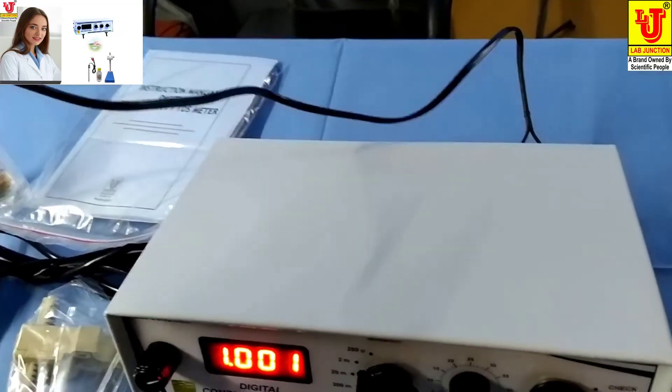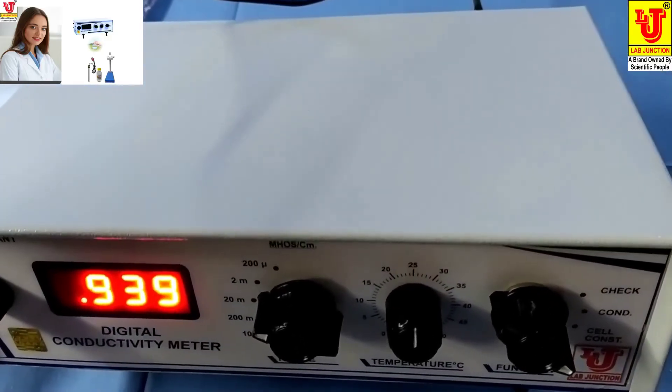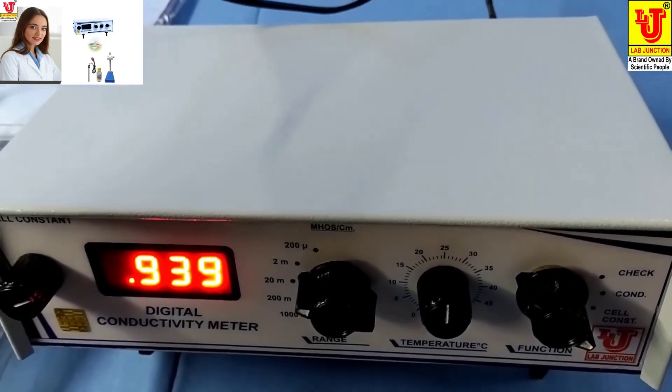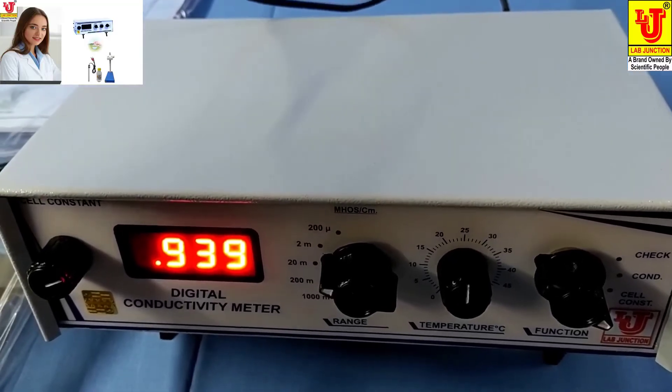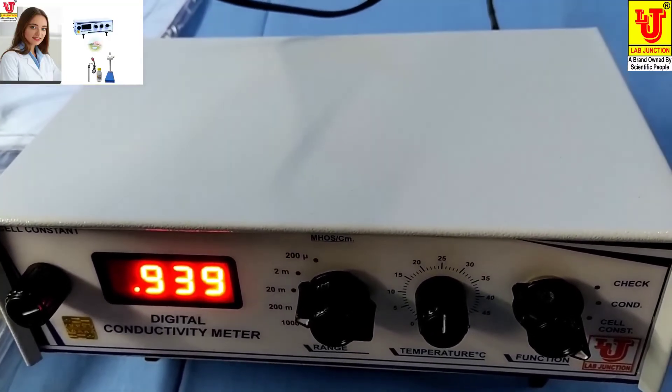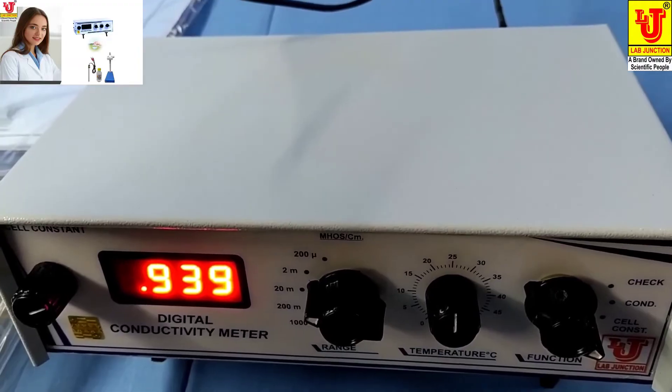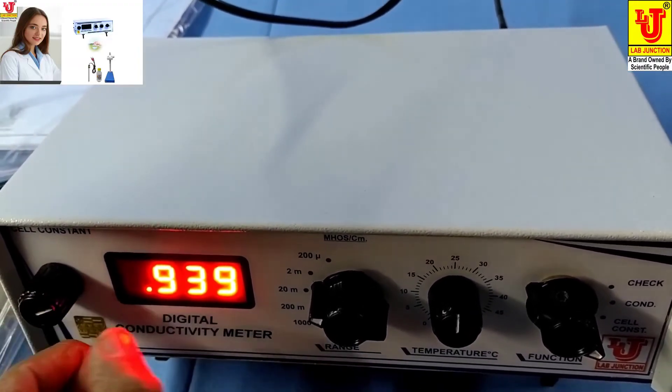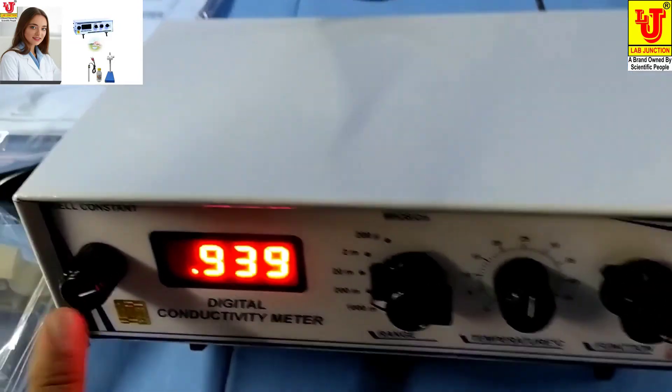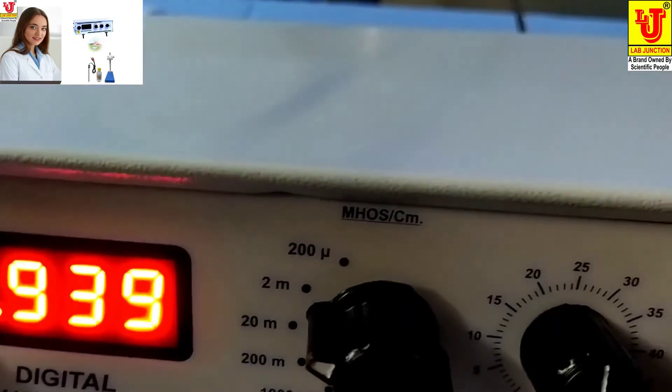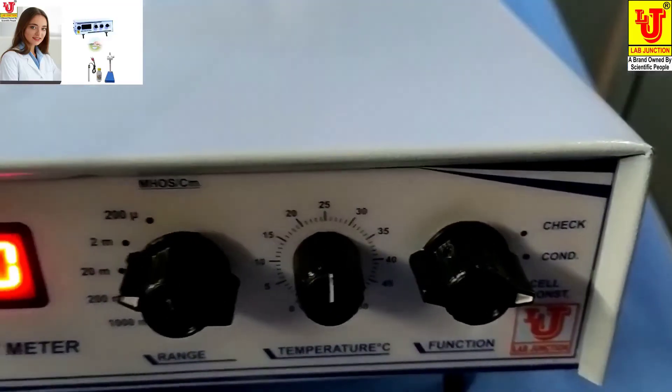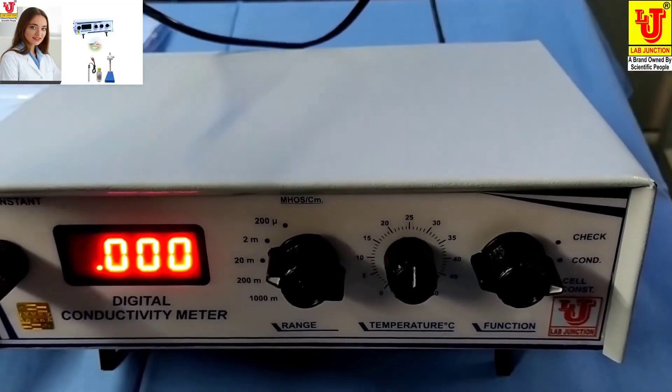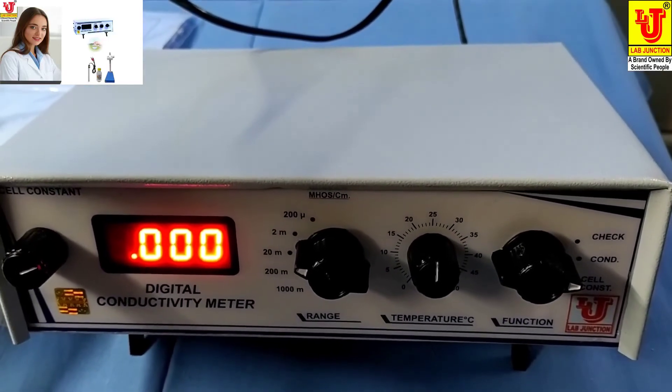Now you directly go to cell constant. You have noted 0.939 on your notebook. Then insert same value with the help of cell constant knob, 0.939 from cell constant knob, and go to conductivity. Again, your digital conductivity meter is ready for use.